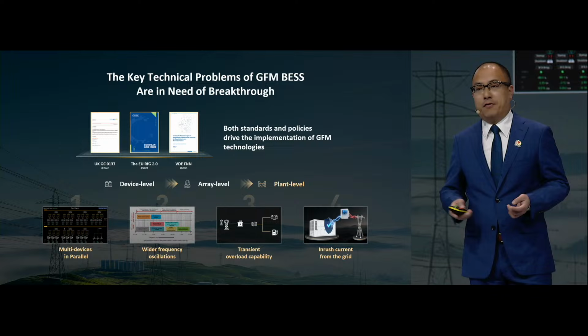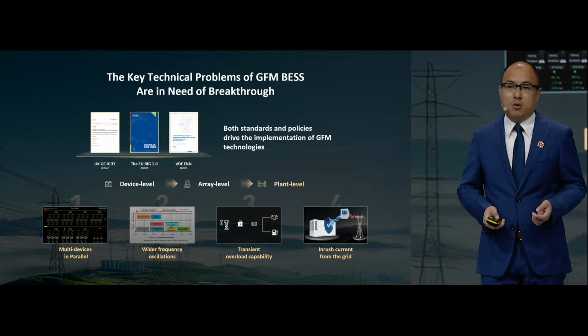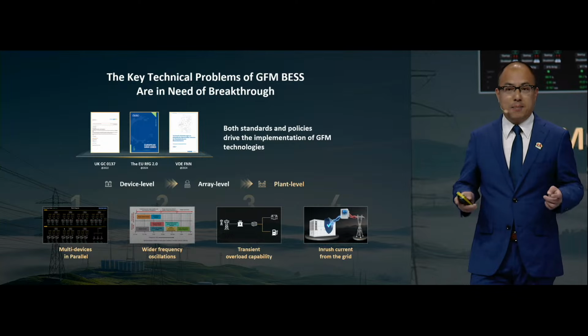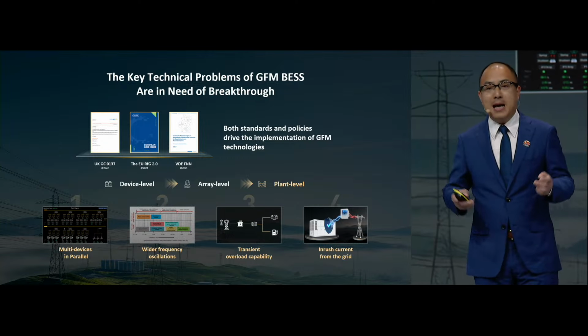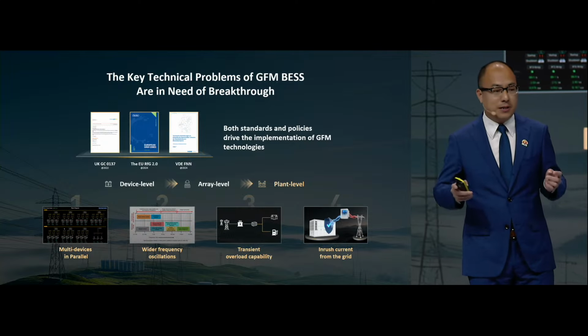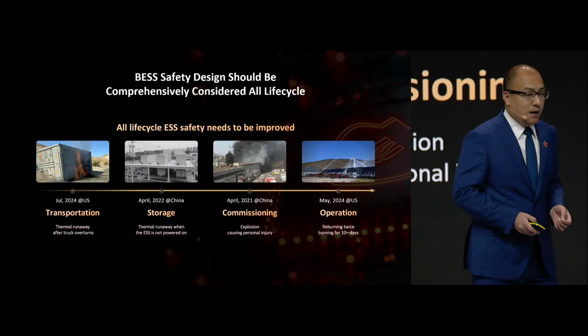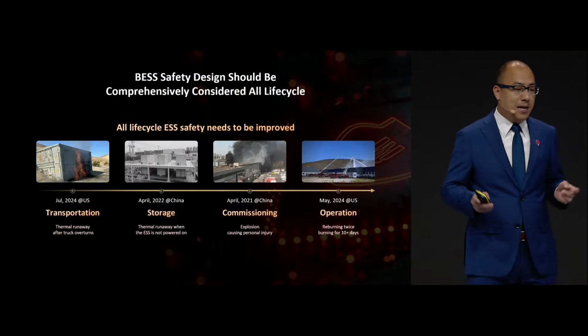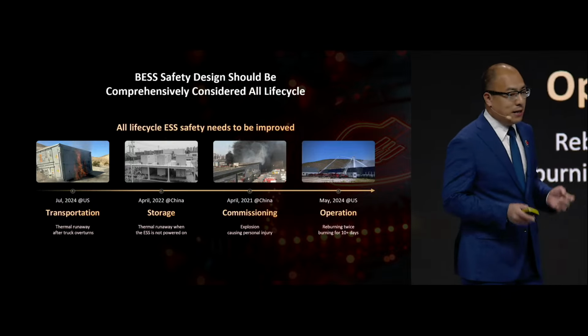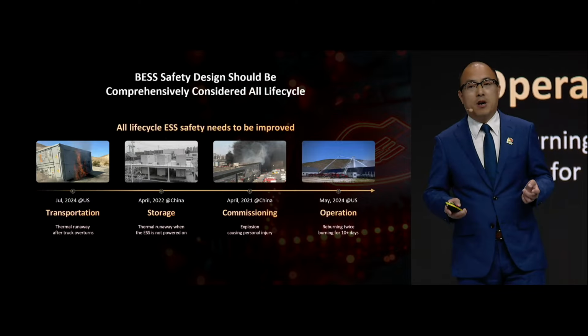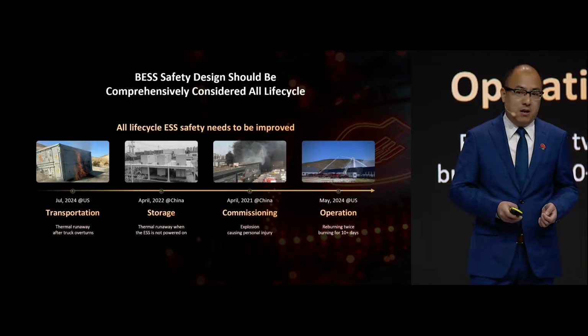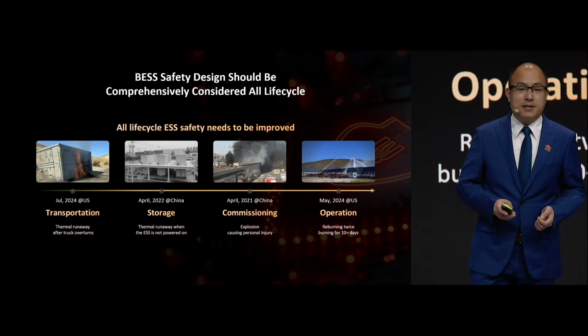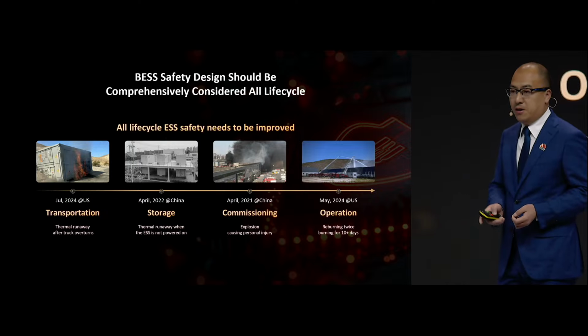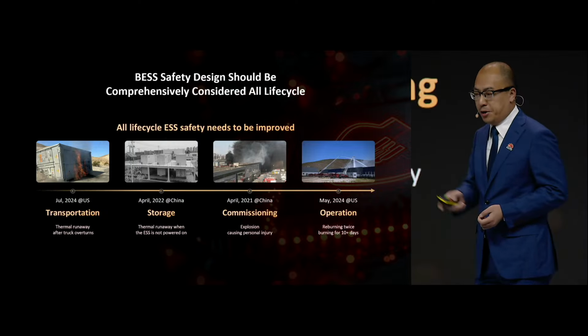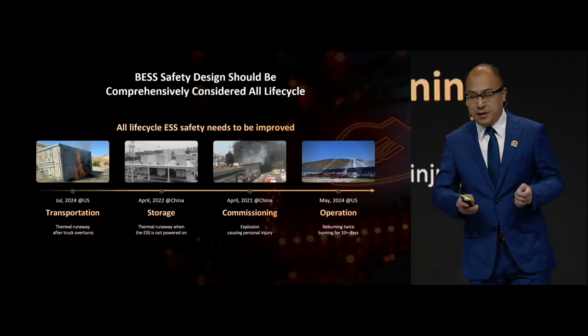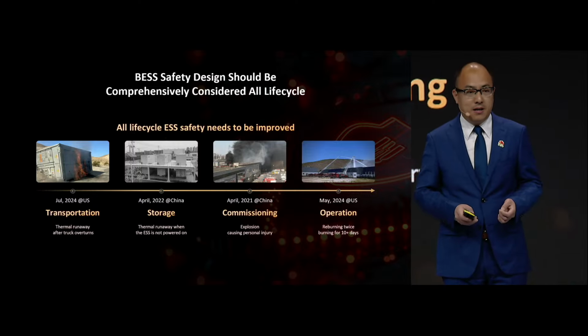The breakthrough of the above 4 technical problems is not only at the device level, but more importantly, at the plant level. We believe that plant-level grid-forming can lead to larger-scale application. Safety is the foundation of BESS business. Now, more BESS safety accidents are reported during operation, but in fact, over 60% of BESS accidents occur in transportation, storage, and even commissioning. Therefore, the best safety design needs to be considered in the whole life cycle.